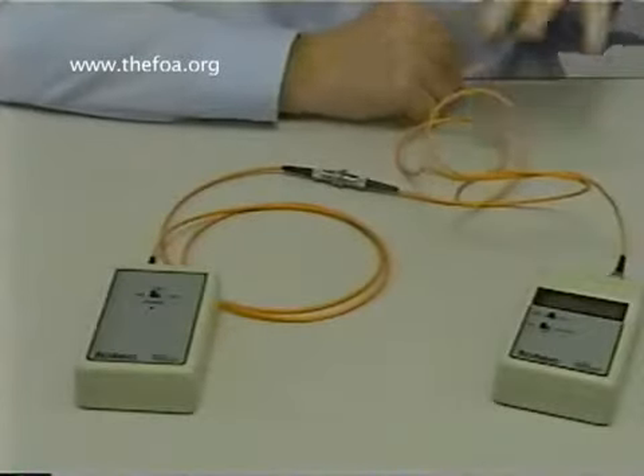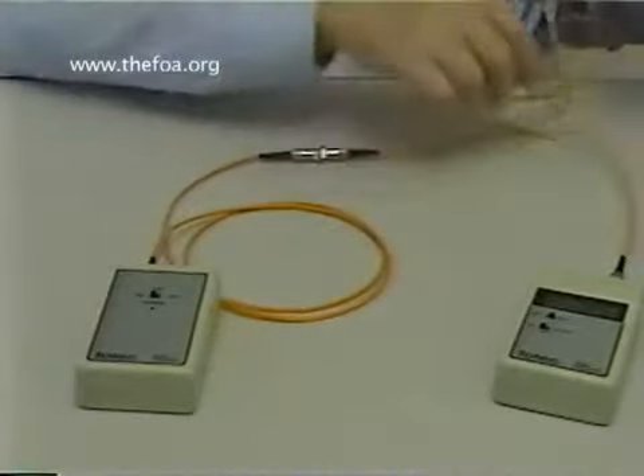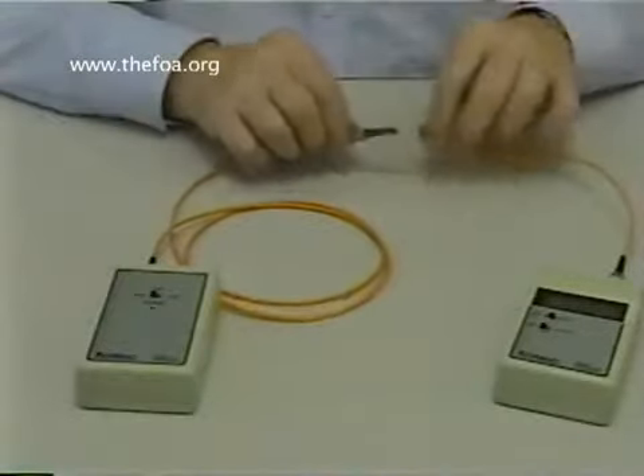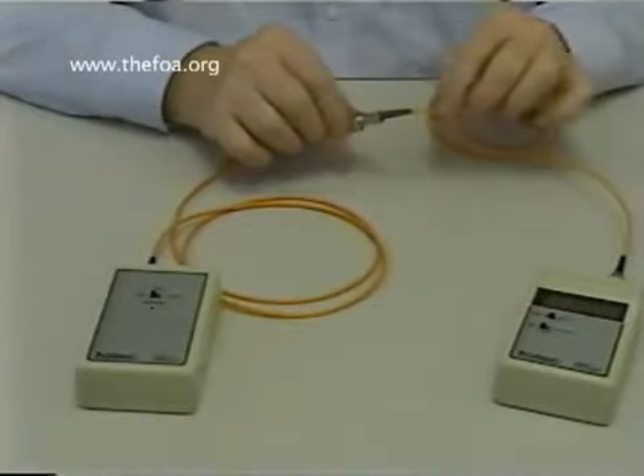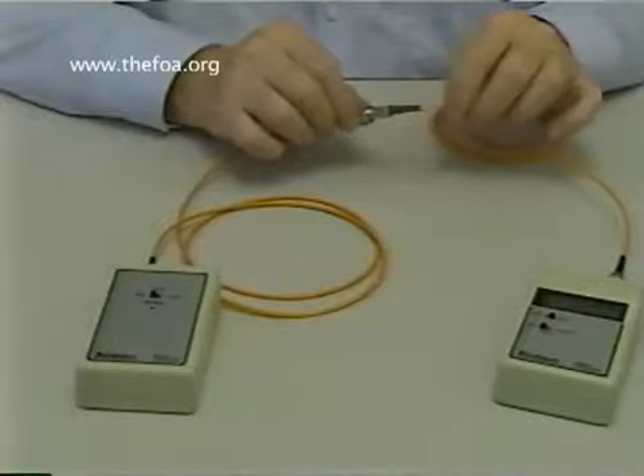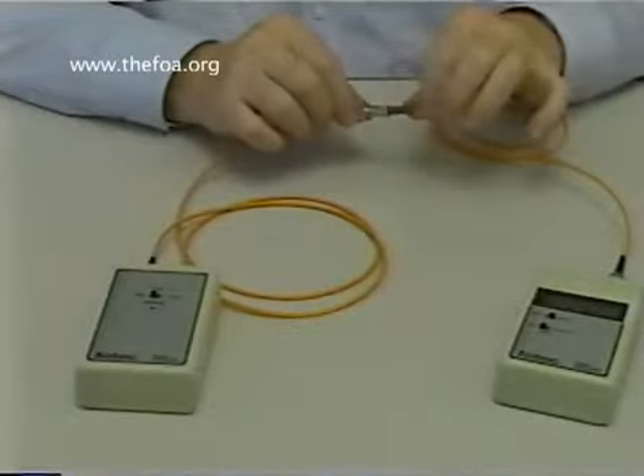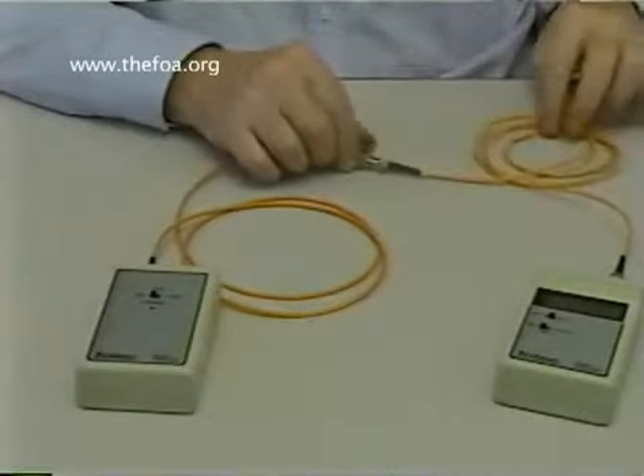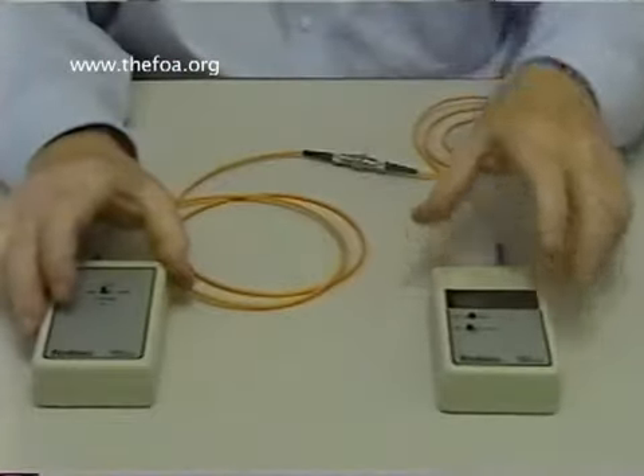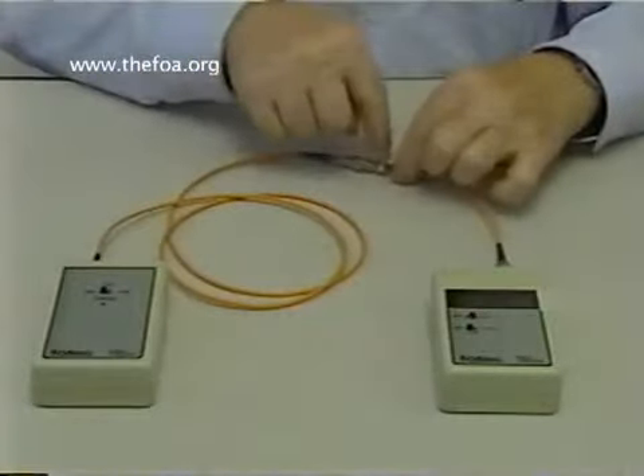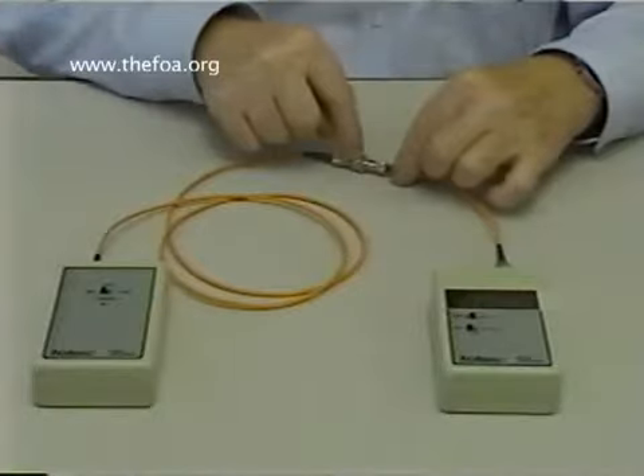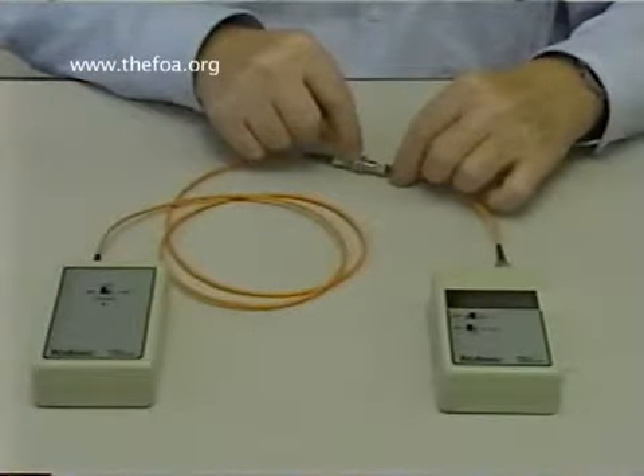So fiber cable is very rugged, and you won't harm it in normal usage, but it will cause variations in the loss if you bend it, particularly around the back of the connectors, and that's the most fragile place where it can be broken. This is what we call a single-ended test. It's single-ended because we're only testing the connector that's mated to the reference connector.